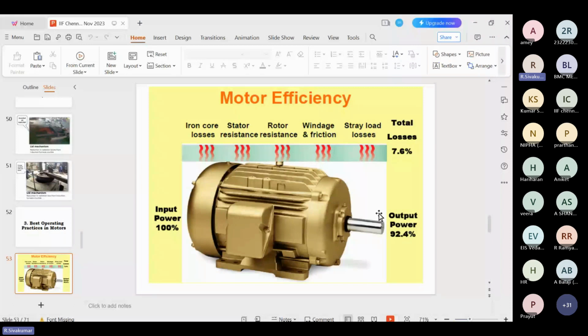Once the motor goes for rewinding, the efficiency drops by a minimum of 2%. If a motor has a lifespan of 10 or 15 years in a foundry, a classical example is EOT crane motors, which fail frequently, and the shot blast machine or any grinding machine motor fails. If the motor is rewound more than 5 to 6 times, then the efficiency drop will be more than 15%, so it leads to more energy consumption. As per the BEE, the Bureau of Energy Efficiency, it also informs all industries not to rewind a motor more than 3 times. Once 3 times is crossed, better to replace the motor with an energy efficient motor, because in the life cycle of any motor the energy consumption is very high.